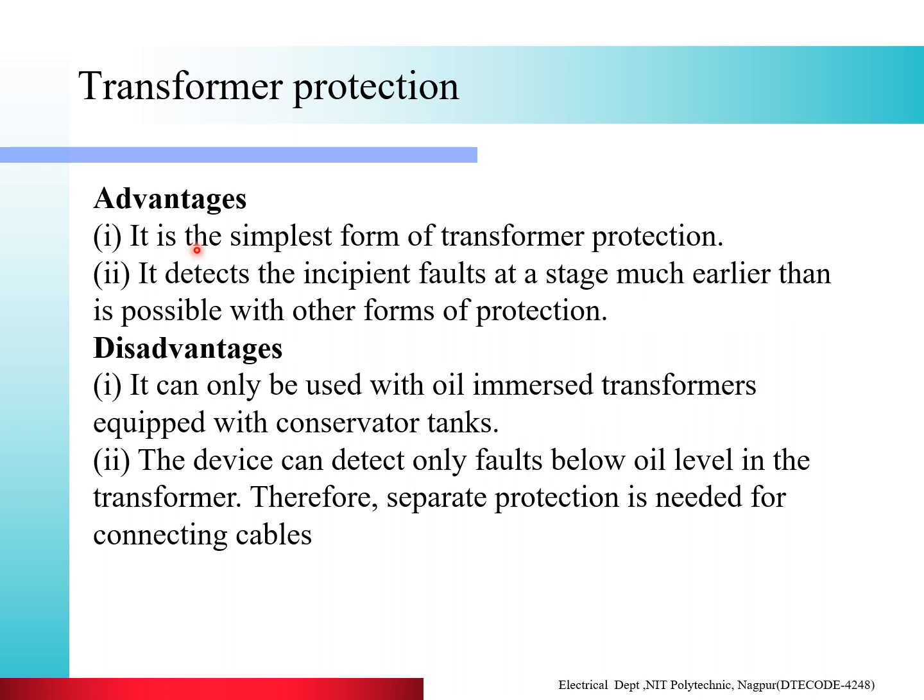So, the advantages of this Buchholz relay. First advantage is it is the simplest form of transformer protection. Second, it detects the incipient fault, that is the slow developing fault, at a stage much earlier than is possible with other forms of protection. So we can carry out maintenance of the transformer, and you will save your power transformer from breakdown.